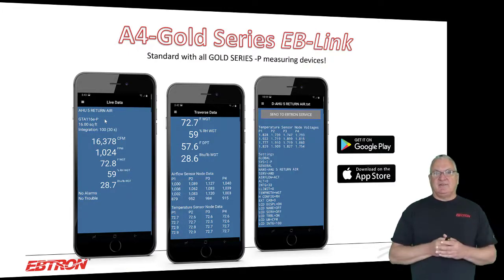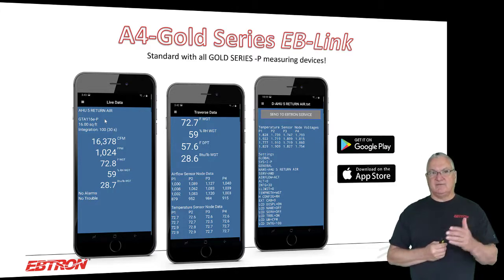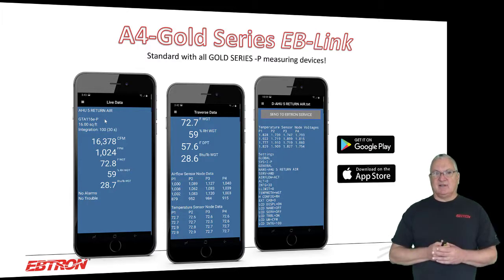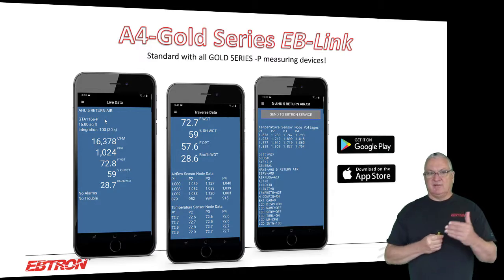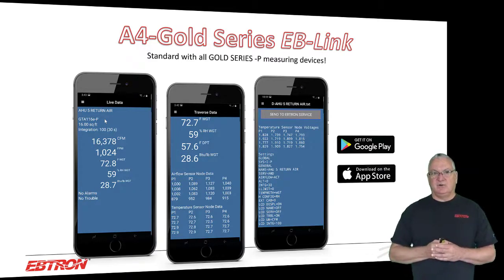We call that the live data screen. The traverse data screen will give you the individual sensor node airflows and temperatures. And then we have a diagnostic screen that'll do everything that our diagnostic mode will do. It gives you all the configuration parameters that you've set it to, and shows you individual sensor voltages and sensor temperatures in real time. It also has a send to EBTRON service button, so that if you're having a problem, you just send this data to EBTRON and it will facilitate any of your service issues.